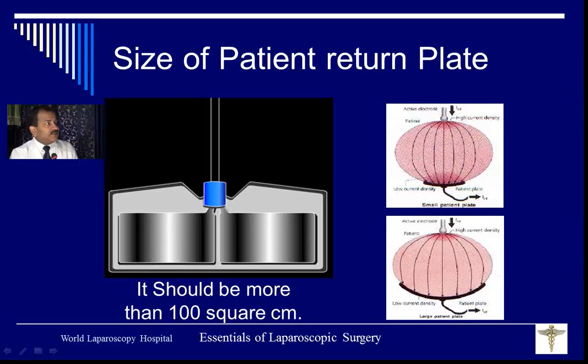If this is the electrode and this is the patient return plate, and your patient return plate is small, less than 100 square centimeter, and 100 square centimeter is not a big area. 100 square centimeter means 10 by 10 centimeter. Of this palm, that much is 100 square centimeter, about 1/4 of this. At least that much area must be in contact, 10 by 10 centimeter.